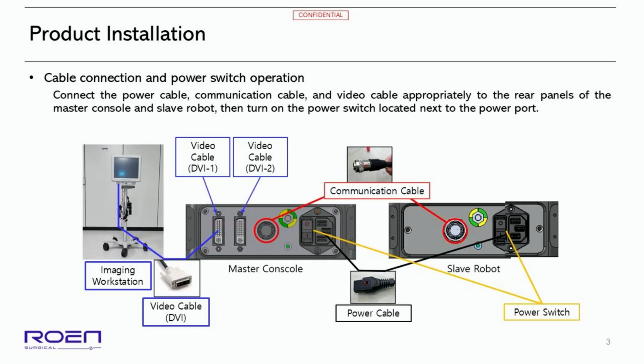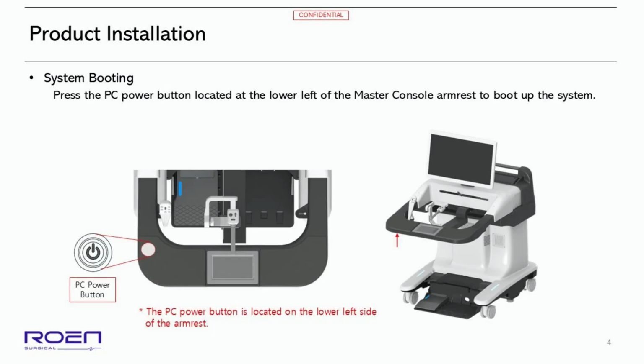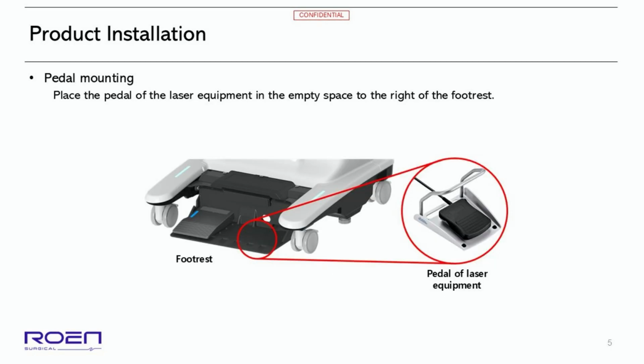Connect the power cable, communication cable, and video cable appropriately to the rear panels of the master console and slave robot. Then turn on the power switch, located next to the power port. Press the PC power button located at the lower left of the master console armrest to boot up the system. Place the pedal of the laser equipment in the empty space to the right of the footrest.